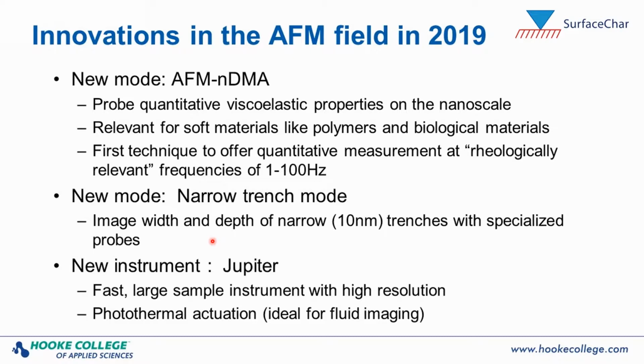And then finally, I'm going to talk about a new instrument that was introduced to the market. At this point, it's not so often that we get a brand new instrument, brand new platform that was designed from the bottom up. But this year we did. There is a new entry to the market. It's called the Jupiter. It's a fast, large sample instrument with high resolution, and I'll discuss why the combination of that is not so easy to achieve. And another differentiating factor on this instrument is that it enables photothermal actuation in addition to piezo actuation, which is what you really want for fluid imaging.